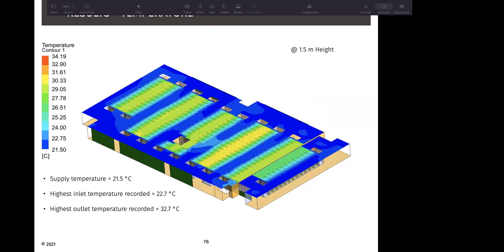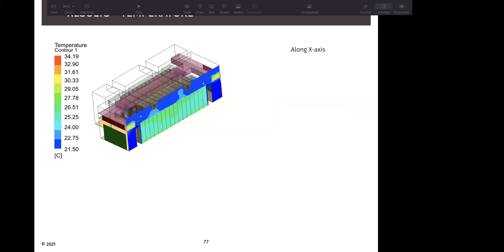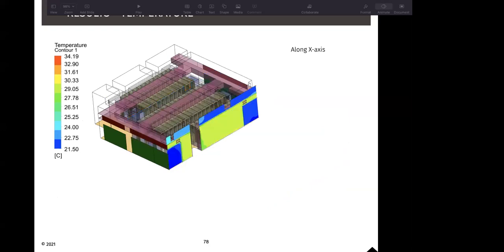And we can also study whether the supply temperature reaching every rack is within optimum limits. If you want to maintain it at 21 or 22 degrees, what is the highest inlet temperature which is recorded, what is the highest outlet temperature which is recorded, and whether it is being maintained in a proper manner. For this particular case, we have the supply temperature at 21.5 degrees, and the highest inlet temperature recorded was 22.7 degrees for the hot aisle contained data center. We can record the inlet temperature and the outlet temperature for each server rack to study whether it is properly maintained. Looking at the section for the same, we can see that the hot aisle containment is somewhere around 30 degrees.